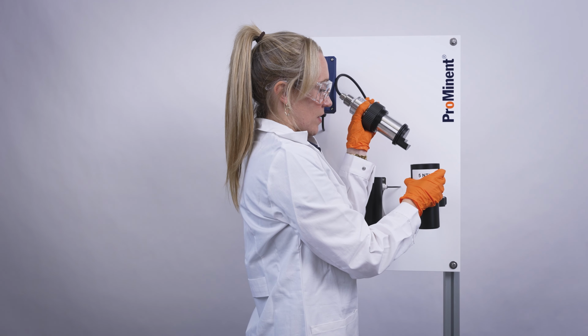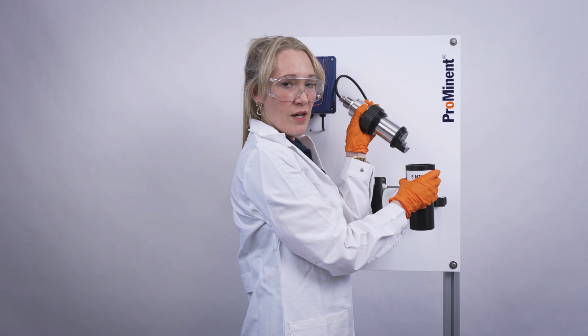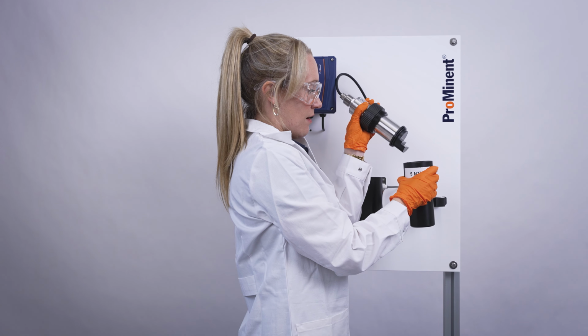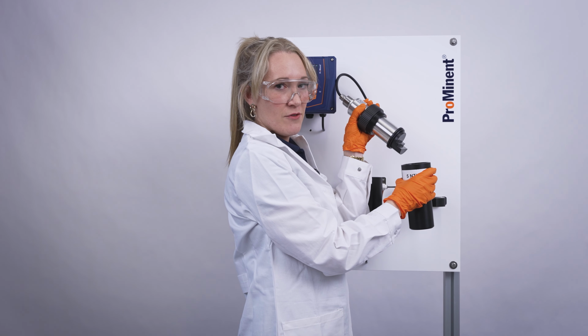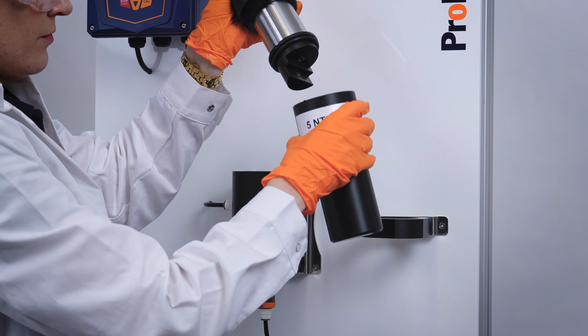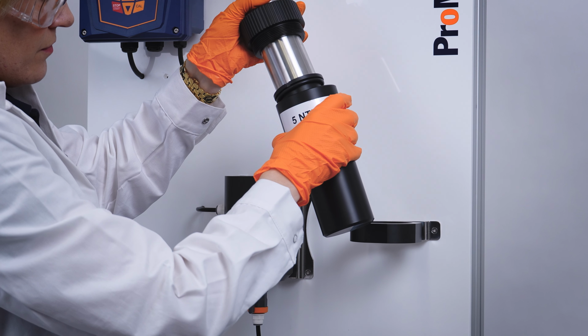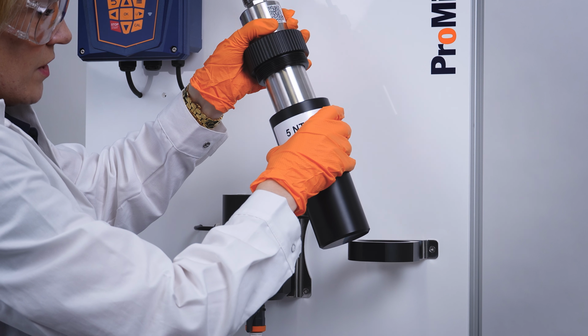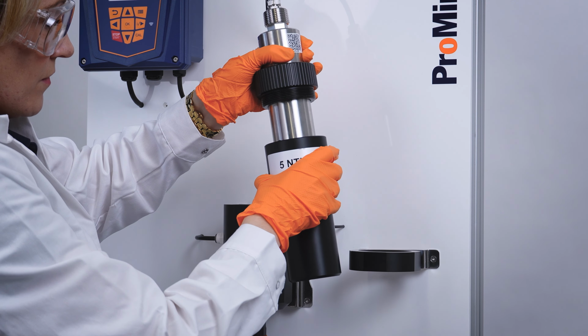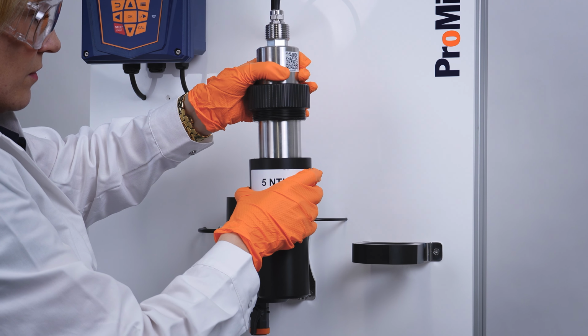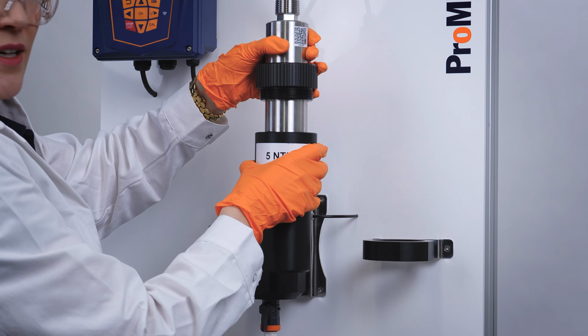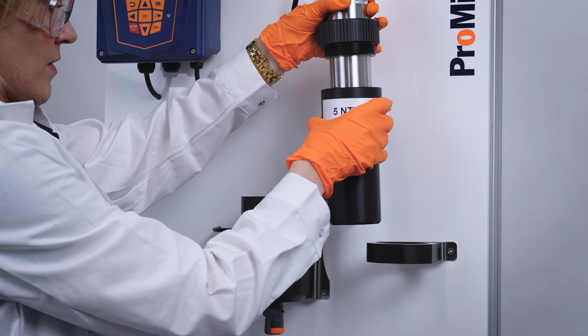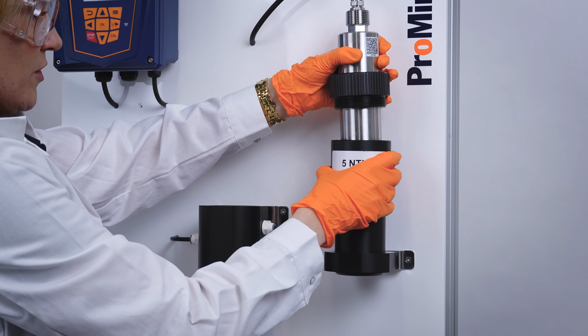And now when you put those parts together, you have to make sure that both are at an angle of, let's say, 45 degrees to prevent air bubbles from being trapped under the sensor. Slowly insert the sensor. Put it in vertical direction. And then back to the holder.